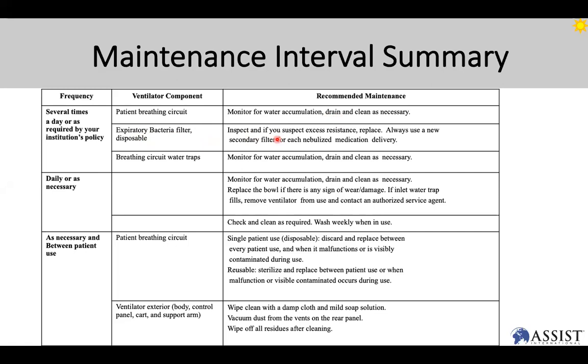Always inspect this filter, and if you see any excessive resistance in the breathing circuit, you replace. And again, overall, for a ventilator, you're always constantly monitoring for water accumulation, and you're always monitoring the condition of the filters, the heat and moisture exchange filter, as well as the HEPA filter. As necessary, between each patient, if it is a single-use disposable circuit, you encourage them to discard that appropriately. If it's reusable, you will sterilize and replace it between each patient. The outside of the ventilator, the body, the control panel, the cart, the support arm, you will wipe down with a clean, damp cloth and mild soap solution.